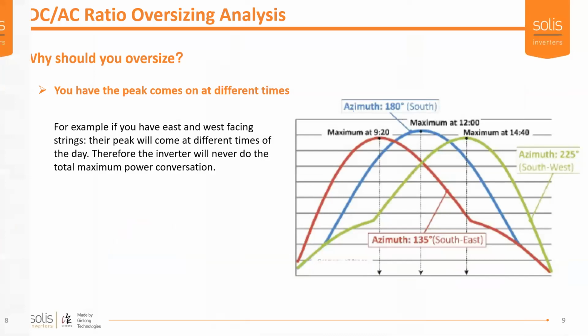Even better than overrating it all at the same time in the day is having your peaks happen at two different times of the day. Since most of our inverters have independent trackers, you can put a portion of the PV on one tracker and the rest on the other tracker. Or if you have multiple trackers, you can spread it out evenly. By doing this, the inverter doesn't have to convert all the power at the same time.